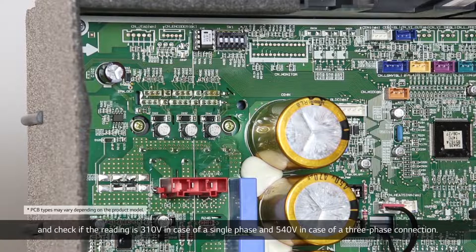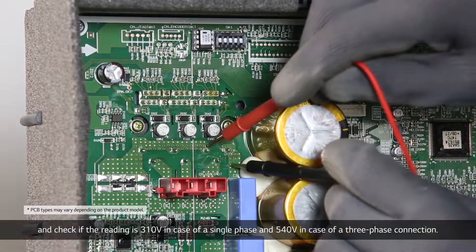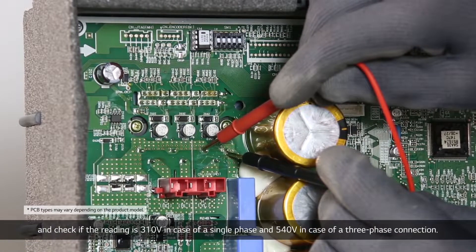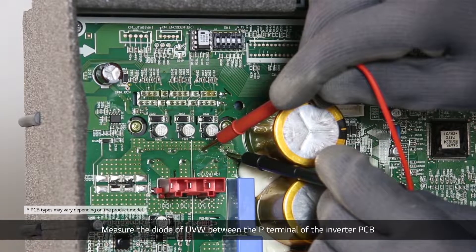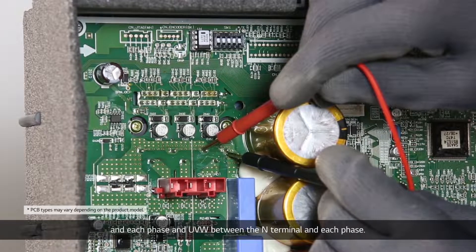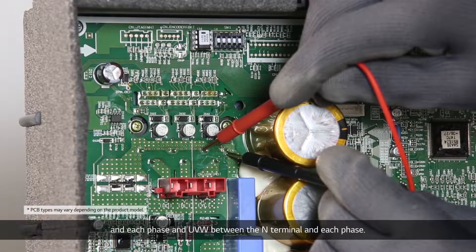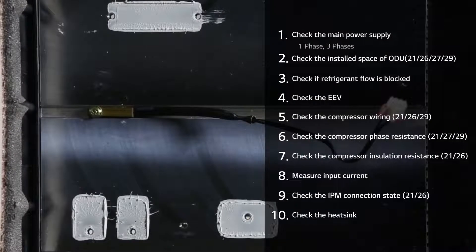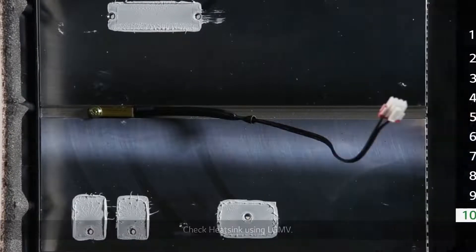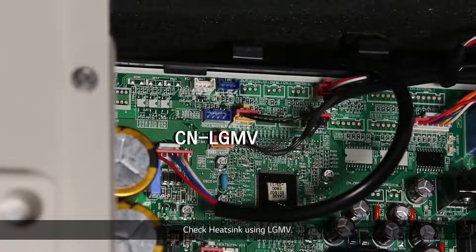Measure the voltage at terminals P and N of the inverter PCBA DC link, and check if the reading is 310V in case of a single-phase and 540V in case of a three-phase connection. Measure the diode of UVW between the P terminal of the inverter PCBA and each phase, and UVW between the N terminal and each phase. Check the heatsink using LGMV.